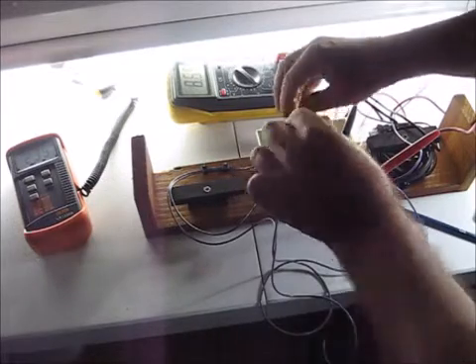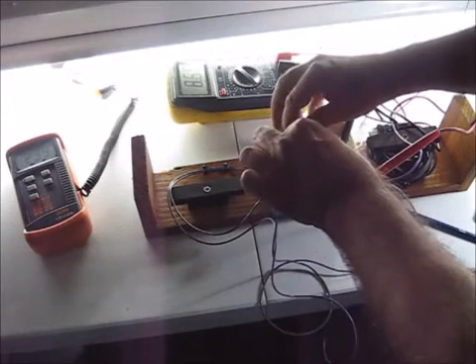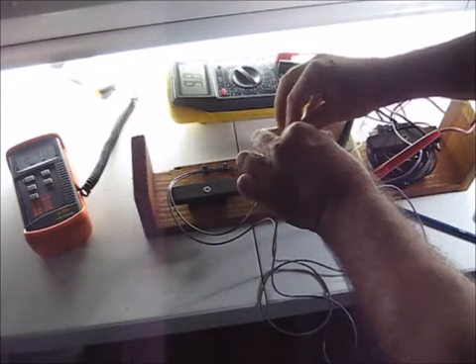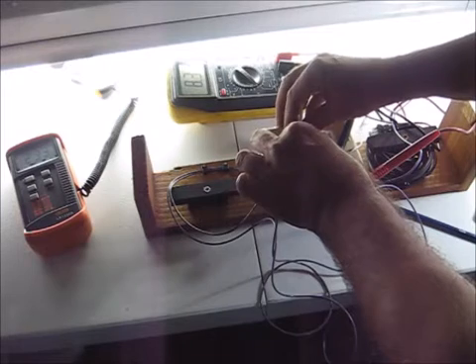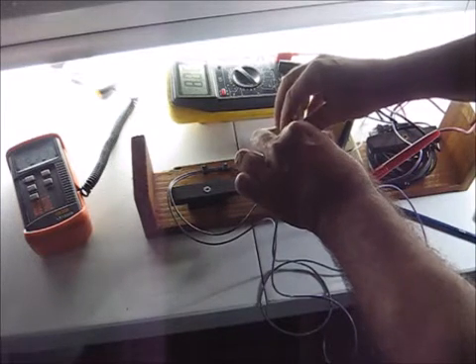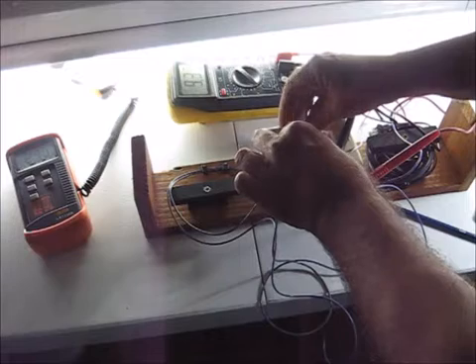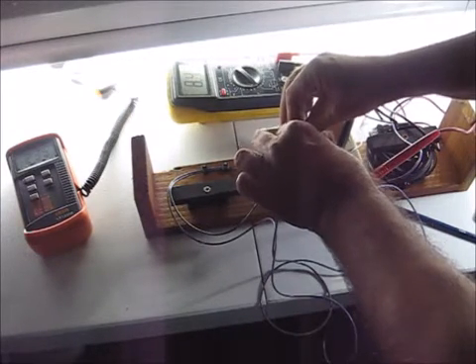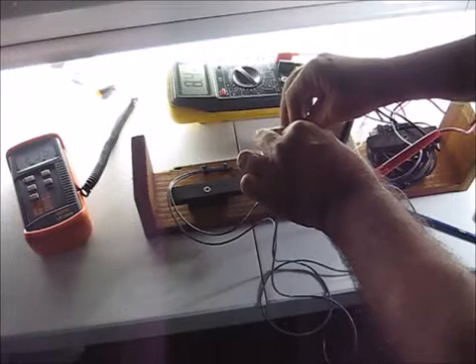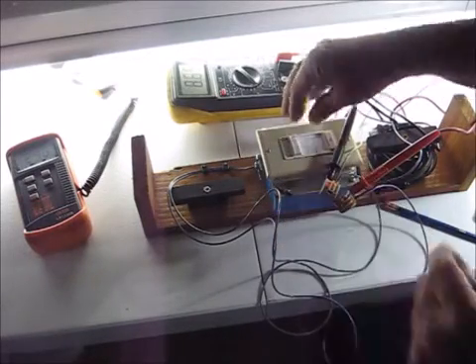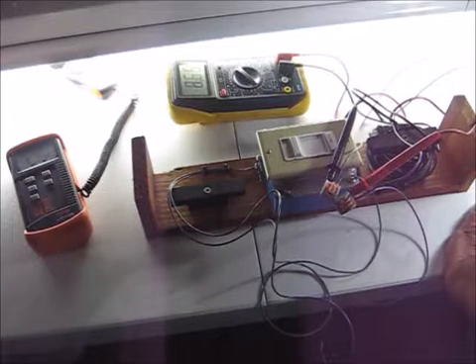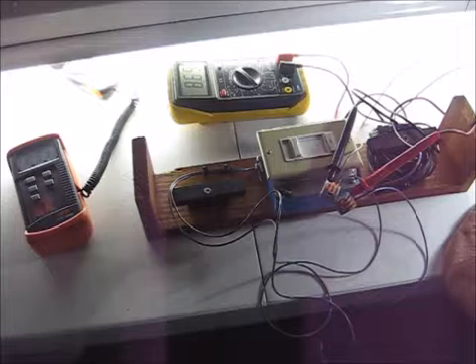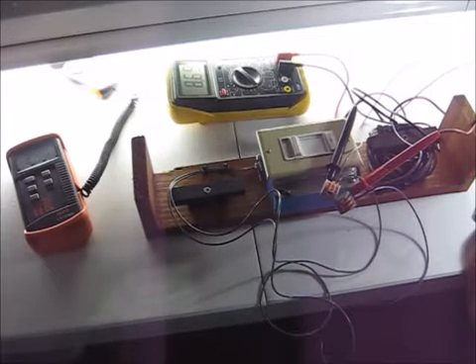8.6, maybe that's about the top end. Let me drop it just a hair. Somewhere around 8.3, it's definitely dimmed. Touchy, touchy. 8.25, definitely dimmed a little. 8.4, definitely dimmed a little. 8.6 all the way up. I'm going to call it 8.5 volts would be the 0 to 10 volt control voltage where this thing starts to dim down.